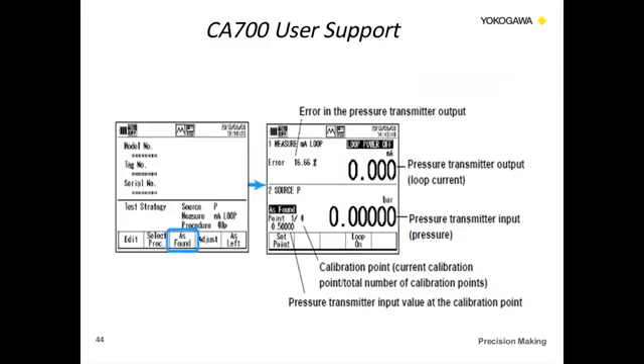So when we go into the calibration part of it, this is where you do your as found, as left procedure. So when you see the model number, tag number, serial number, you can scroll up to there and actually input that information. So you could actually input the information from the manufacturer you're using, the tag number that's assigned to the device, and also the serial number to the device. And once you enter this information and you perform your testing, that information will be saved in the CSV file.